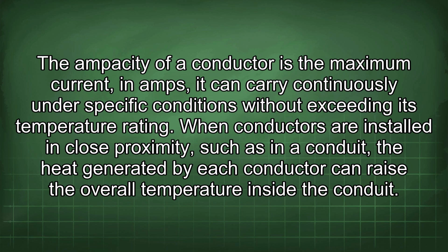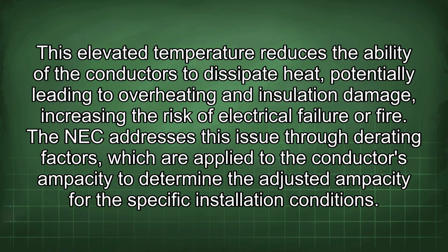When conductors are installed in close proximity, such as in a conduit, the heat generated by each conductor can raise the overall temperature inside the conduit. This elevated temperature reduces the ability of the conductors to dissipate heat, potentially leading to overheating and insulation damage, increasing the risk of electrical failure or fire.